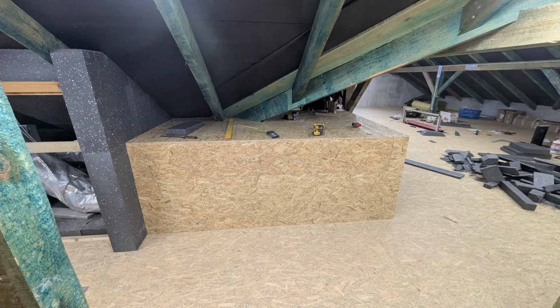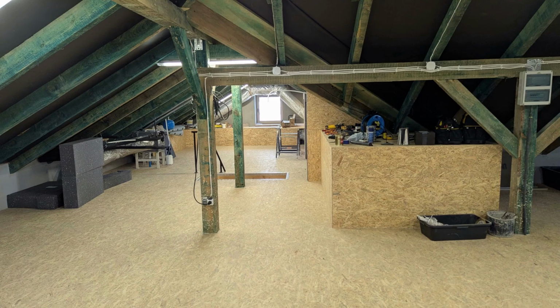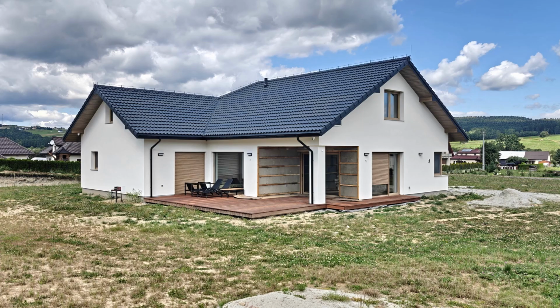Currently, when operating at the first and second speeds, the noise is completely inaudible or almost entirely inaudible. However, in action at the third speed, both ventilation and recirculation are already perceptible. To conclude, the system works just as it was designed. It delivers fresh air to the building around the clock, simultaneously helping to maintain the desired comfortable temperature.